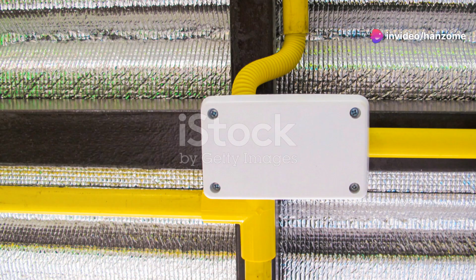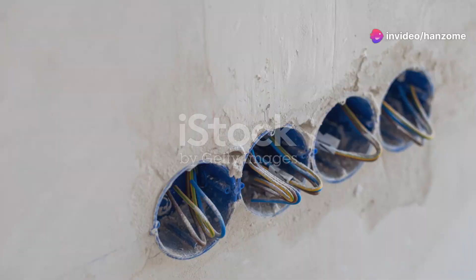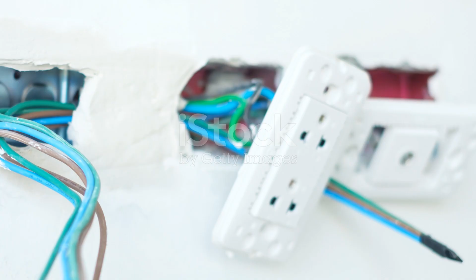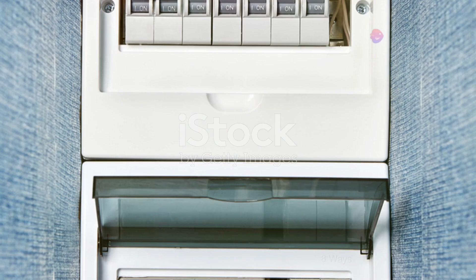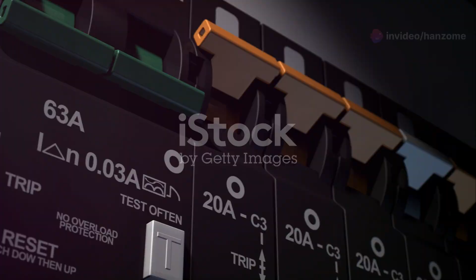Wiring size is also key. It needs to safely conduct the current without overheating. A simple rule: the higher the amperage, the thicker the wire needed. For most household circuits, a 14-gauge wire is suitable for 15 amperes, while a 12-gauge wire is used for 20 amperes. It's all about making sure the wire can handle the load without getting too warm.